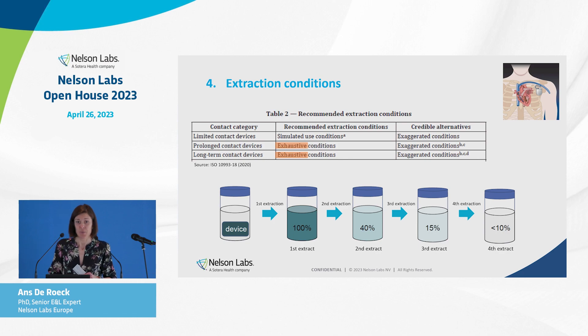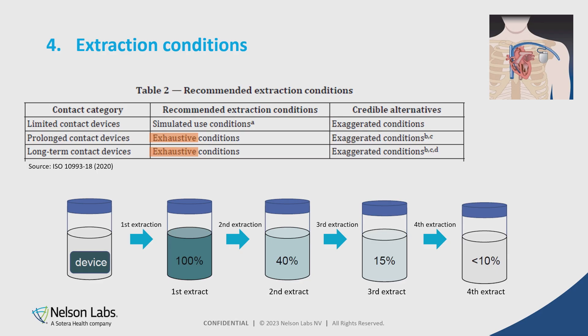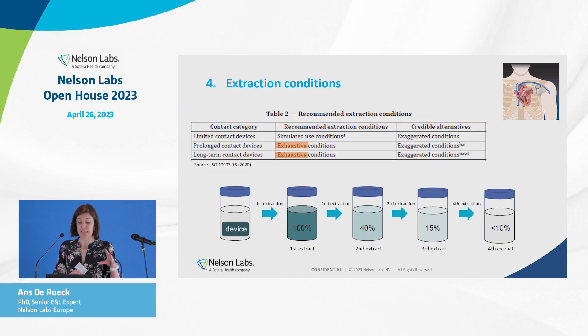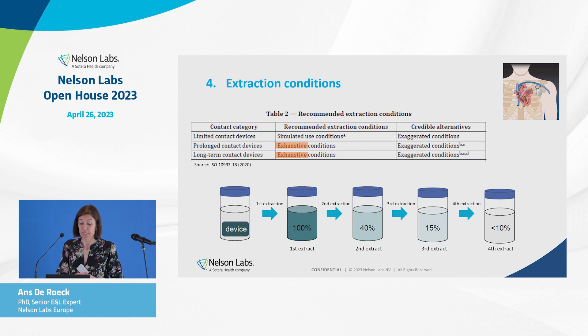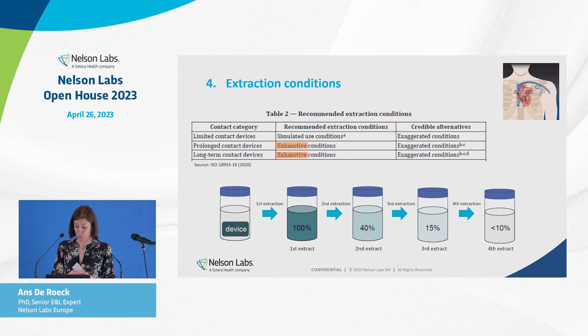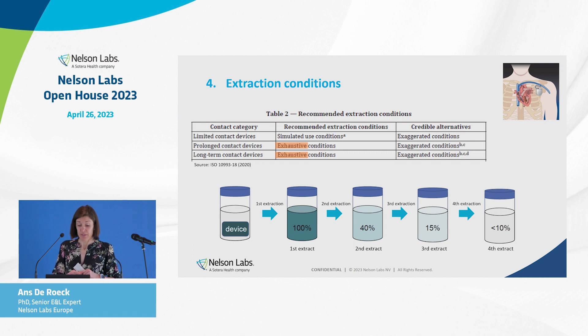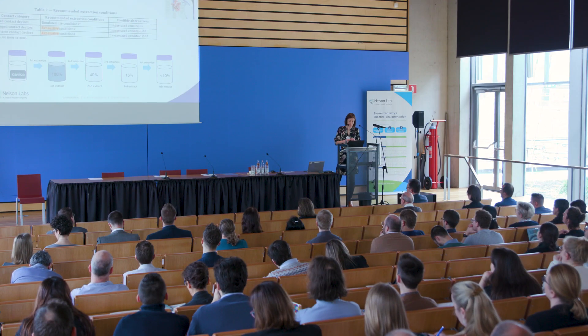For some devices, exhaustive extraction conditions are needed. We determine these beforehand using sequential 24-hour extraction cycles on the same device — extracting for 24 hours repeatedly to obtain several extracts. These extracts are evaporated to obtain the non-volatile residue, measured by balance. From the moment the non-volatile residue is less than 10% of the residue measured in the first extract, the extraction is considered exhaustive. In this example we would extract the test item for 96 hours at 50°C.